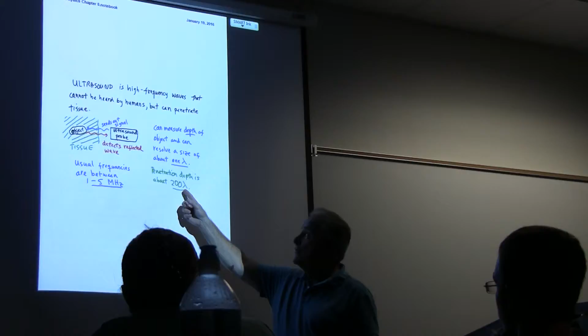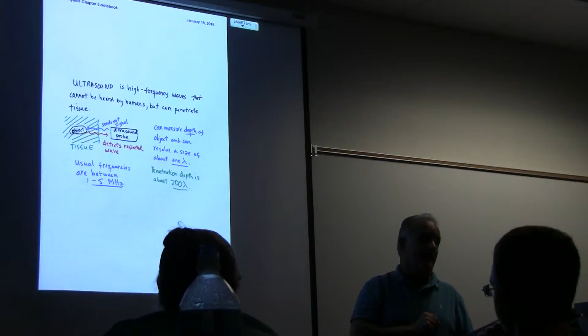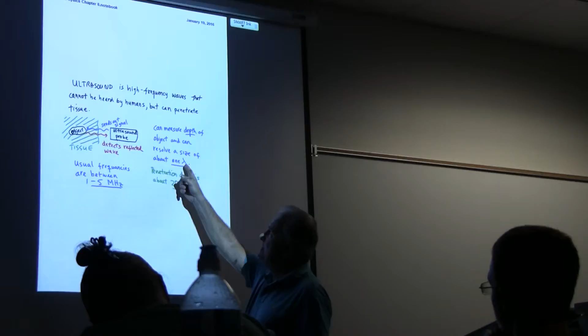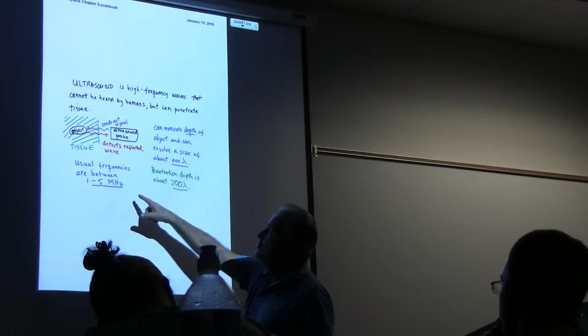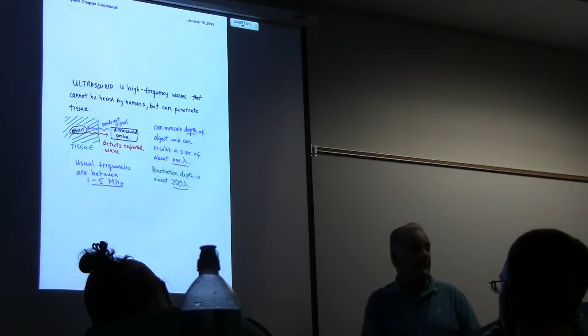frequency if you wanted to look at a baby in the mother's stomach, or you wanted to find a little piece of metal that was in somebody's eye, for example, if they had an accident. You would want to use a different frequency. The other thing is that the size of the object that you can see with the ultrasound probe, the smallest you can see is about 1 wavelength, which is really tiny. So you can see that, based on how deep they want to go and how much they want to be able to resolve the image, they will choose the proper frequency for the probe. Okay, so that's how that works.